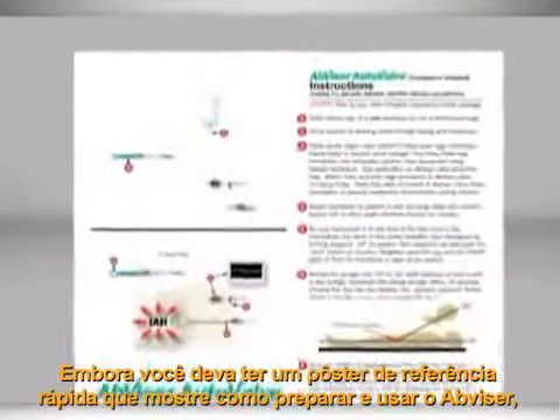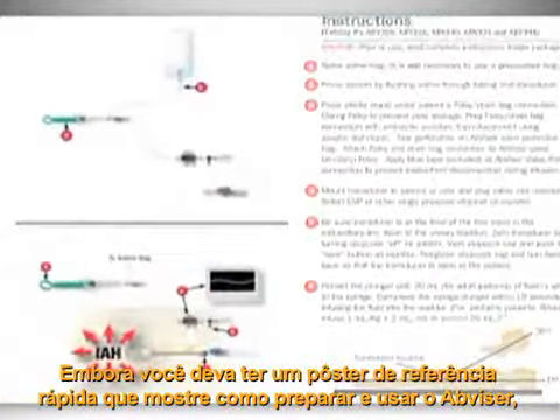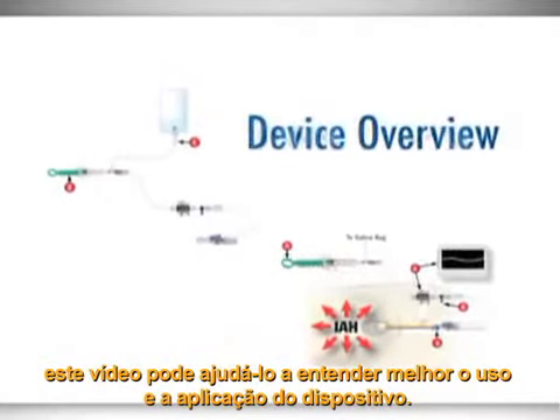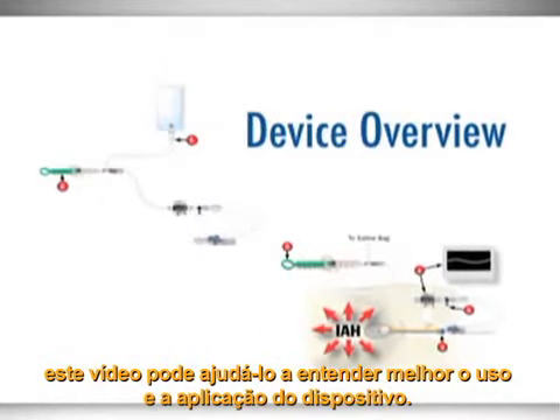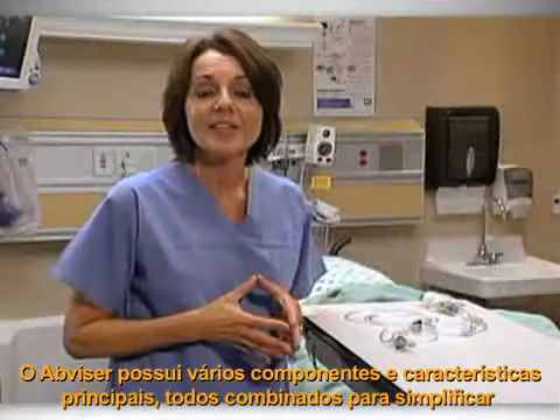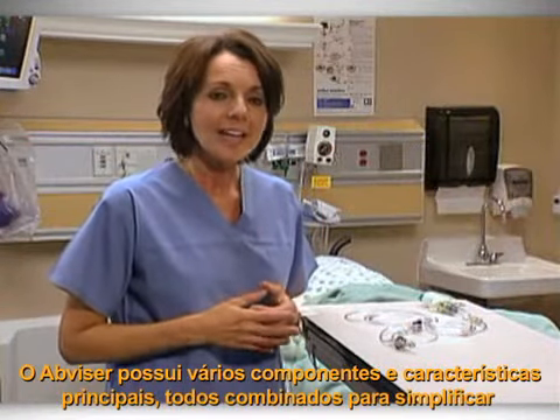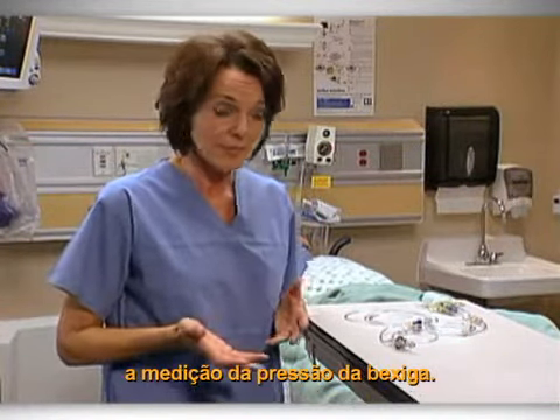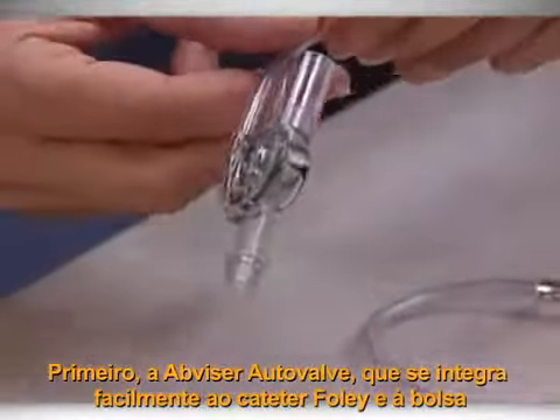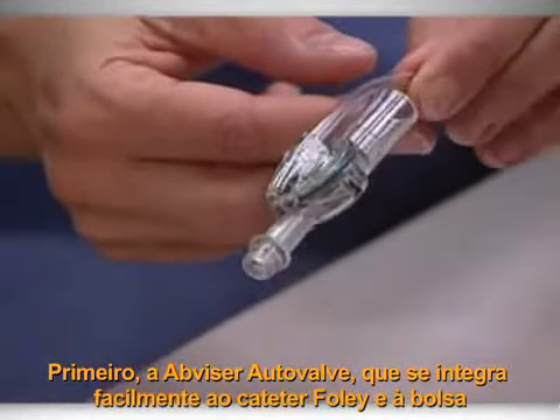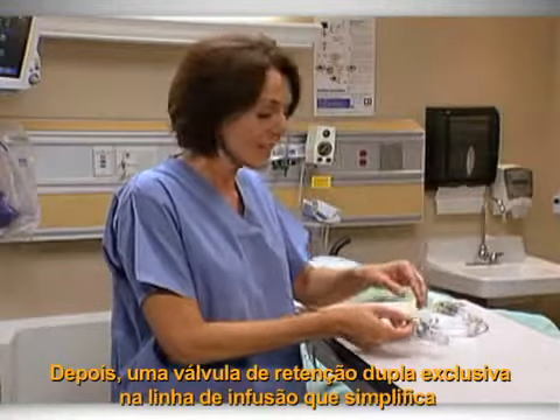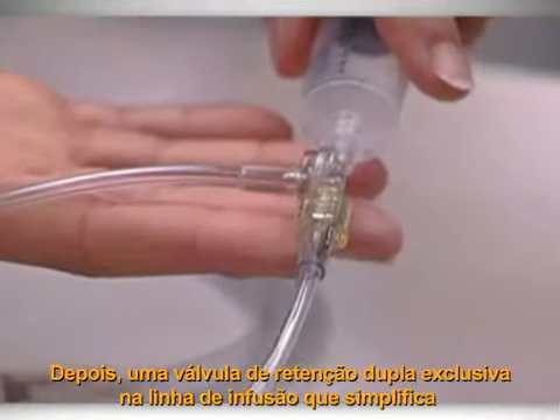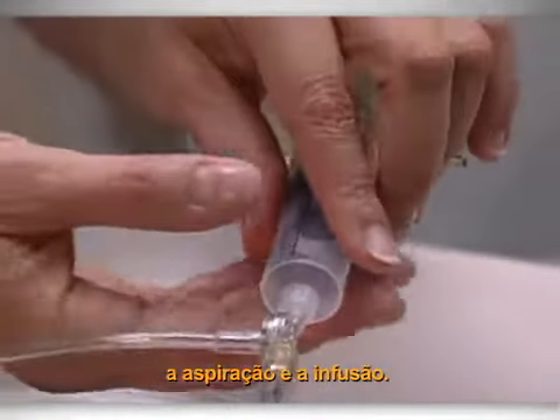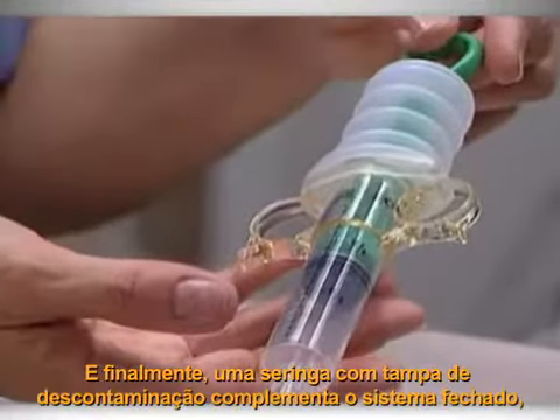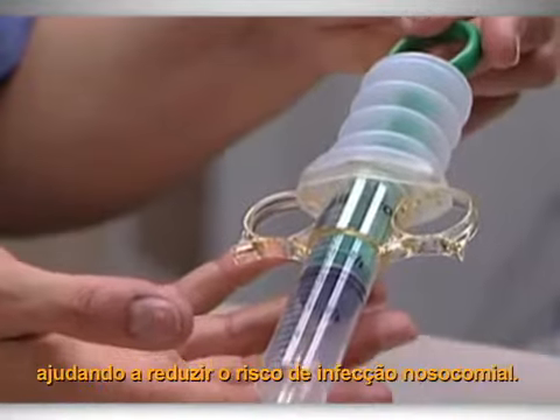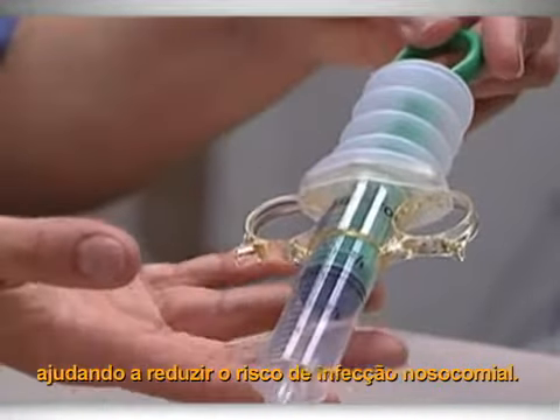Even though you should have a quick reference wall chart that shows how to set up and use the Abviser, this video may help you further understand the use and application of the device. The Abviser consists of several key components and features, all combined to make bladder pressure measurement simple to do. First, the Abviser Autovalve, which integrates easily with the patient's existing Foley and drain bag. Next, a unique double check valve on the infusion line simplifies aspiration and infusion. And finally, a syringe with a contamination shield enhances the closed system, helping to reduce nosocomial infection risk.